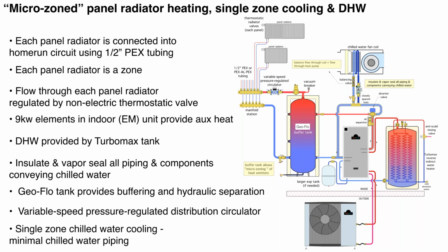And the way the piping is set up here, remember, there is a circulator inside this indoor unit, but that circulator isn't necessarily sized to drive flow at the proper rate through a chill water fan coil. We don't know how big that coil is. We don't know how much piping is between that fan coil and the heat pump. So rather than expect the circulator in the heat pump itself to provide all the flow, I'm using a separate circulator, and we're interfacing that with a pair of closely spaced tees. This is another form of hydraulic separation.